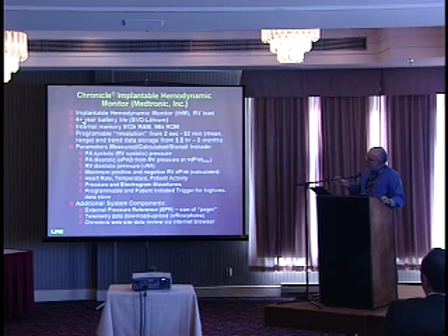The device is implantable, has a 4 to 5 year battery life. It has a significant internal memory, and it's programmable. We can program the resolution. So what it does is it detects the pressures in the right ventricle, measures them over a period of time, anywhere from continuous to up to 30 minutes, and then averages it. And we get lots of parameters: pulmonary artery systolic pressure, which is the same as right ventricular pressure, pulmonary artery diastolic pressure, which is equivalent to left-sided filling pressure. So it tells us the filling pressures on the left side, so the volume on the left side, and the volume on the right side of the heart, because they can be different.